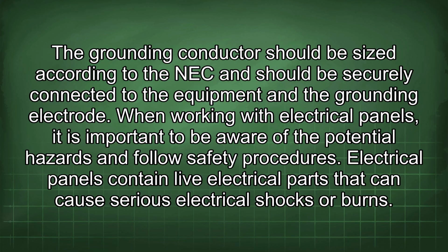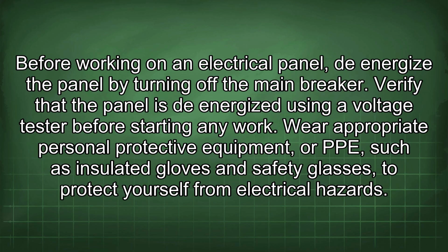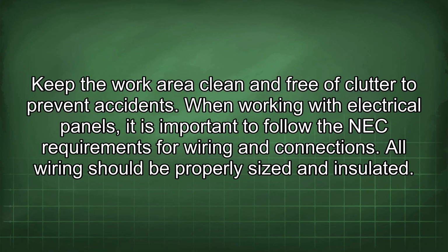grounding electrode. When working with electrical panels, it is important to be aware of the potential hazards and follow safety procedures. Electrical panels contain live electrical parts that can cause serious electrical shocks or burns. Before working on an electrical panel, de-energize the panel by turning off the main breaker. Verify that the panel is de-energized using a voltage tester before starting any work. Wear appropriate personal protective equipment, or PPE, such as insulated gloves and safety glasses, to protect yourself from electrical hazards. Keep the work area clean and free of clutter to prevent accidents.